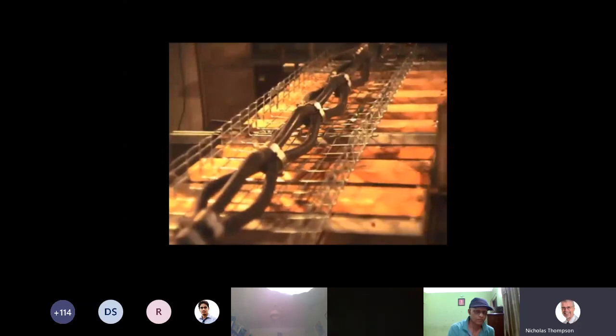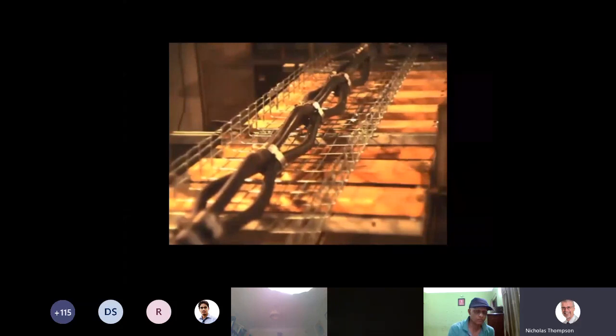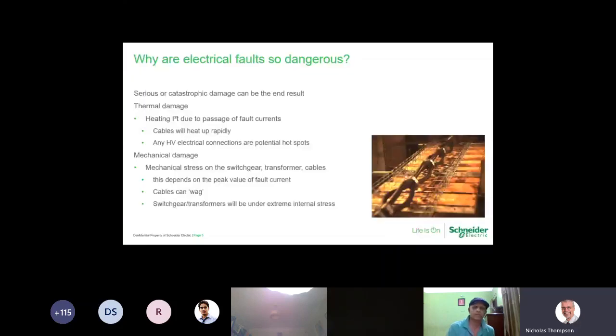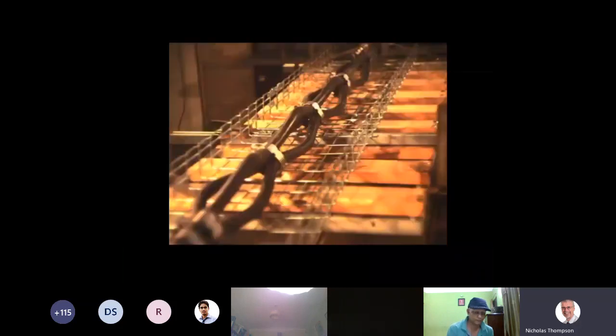Inside a transformer, you've got one pole per phase, which will comprise 2 sets of coils, and once you start to get those reacting, they can literally twist and things can get really distorted inside a transformer. So we've got to be mindful not only of the electrical damage but any potential mechanical damage.